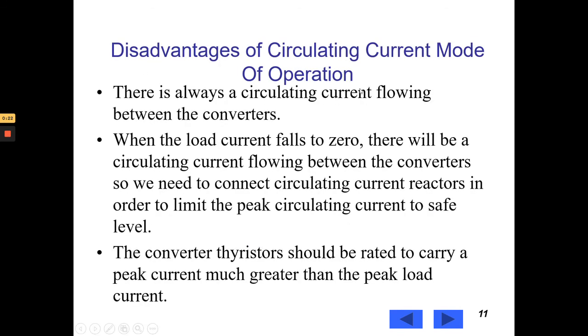Now, we will see disadvantages of circulating current mode of operation. There is always a circulating current flowing between the converters. When the load current falls to zero, there will be a circulating current flowing between the converters. So we need to connect circulating current reactors in order to limit the peak circulating current to safe level.